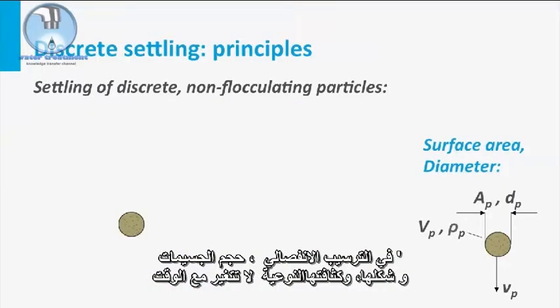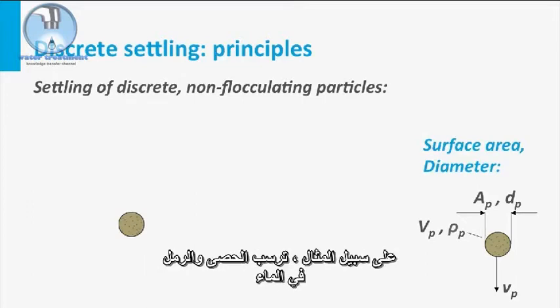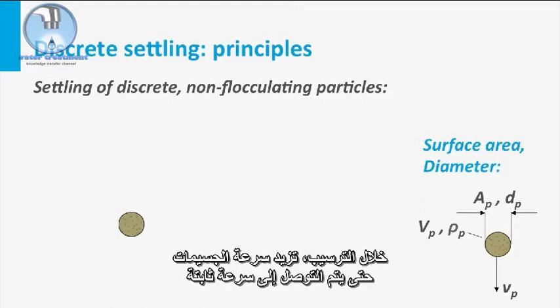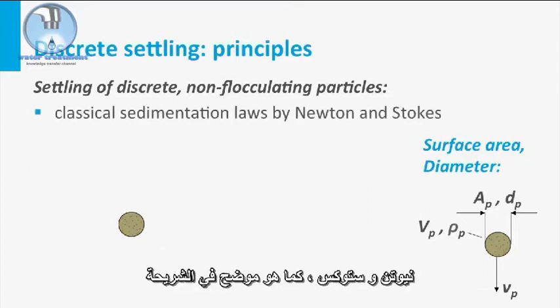In discrete settling, the particle size, shape and specific density do not change in time. Discrete settling is regarded as a non-interactive settling of particles from a dilute suspension — for instance, the settling of grit and sand in water. During the settling, the particle velocity accelerates until a constant velocity is reached. Discrete settling can be mathematically described using the classical sedimentation laws of Newton and Stokes, as illustrated in this slide.